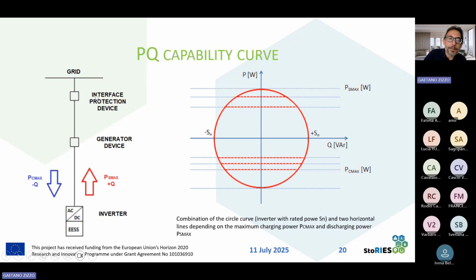We have in this case an interface protection device that is sensitive to the values of the frequency and voltage at the point of common coupling between the storage system and the grid, and is usually set between 90% and 110% of the rated voltage of that system. And you see on the right an example of the PQ capability curve of the storage system coupled with its inverter. The inverter has a rated power indicated by Sn. The storage system has a maximum discharge power indicated by PS max, and the maximum charging power indicated by PC max.